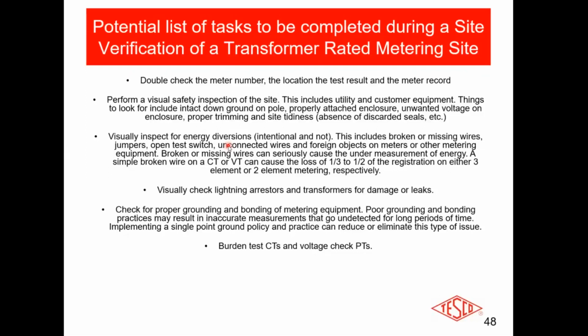The covers are designed, there's an ANSI spec to them, so that when you put that cover on and tighten it down, if you did leave a test switch open, you wouldn't be able to get it on, and if you didn't leave it fully closed, it would actually help to close that test switch. So there's actually a reason for those covers. But if you don't use the covers, you could test a site and leave that test switch open.